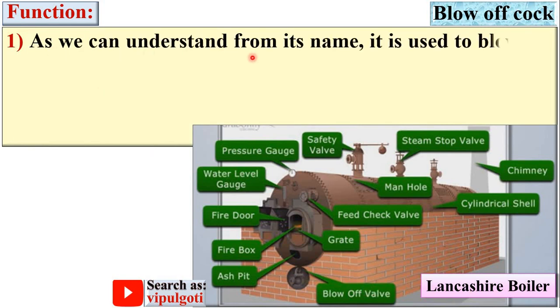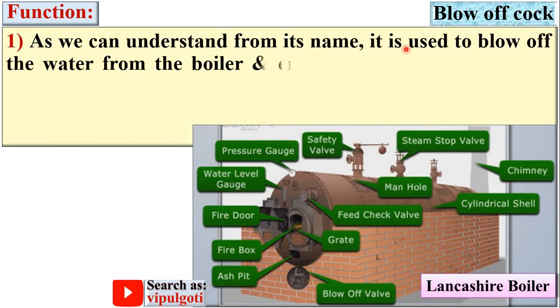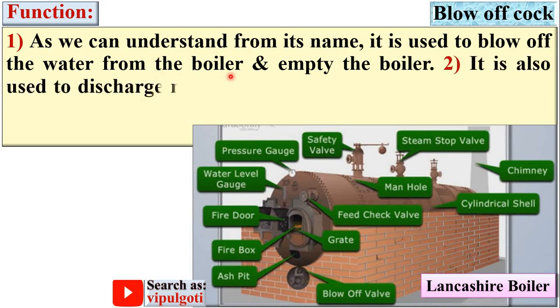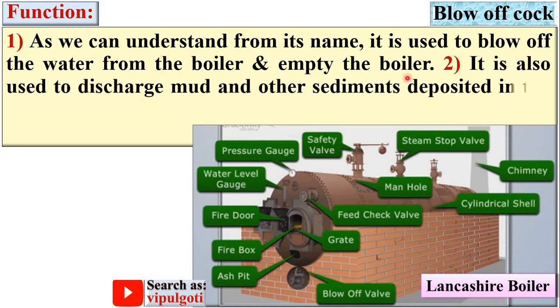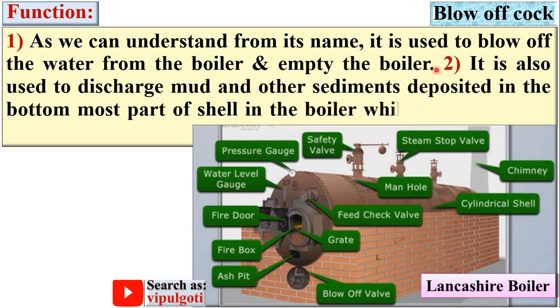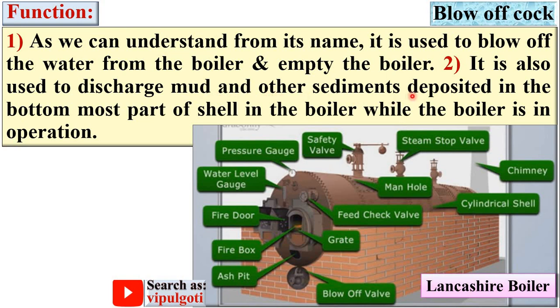The first function of the blow-off cock: as we can understand from its name, it is used to blow out the water from the boiler and empty the boiler. The second function: it is also used to discharge mud and other sediments deposited in the bottommost part of the boiler shell while the boiler is in operation. So if you want to discharge mud and sediments during the working of the boiler, you can use the blow-off cock.